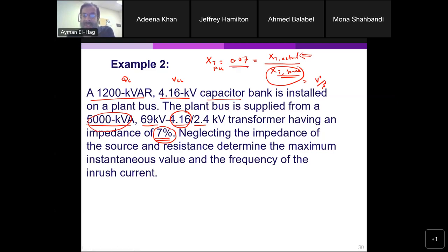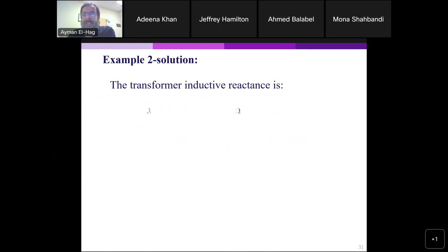Now we'll ignore the resistance, and we ignore the impedance of the source. So this is the only impedance that we have in the system. What is the maximum instantaneous value and the frequency of the inrush current? What is the frequency and what is the value of this inrush current? So the transformer inductive reactance X in ohms, you multiply the per unit times the base. And the base is the voltage, 4.16 kV, because I am interested in the value of X reflected to the secondary side, divided by the 5 MVA. This is your X, the inductive reactance.